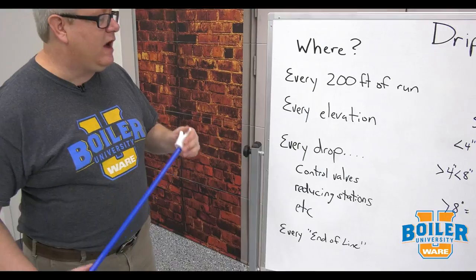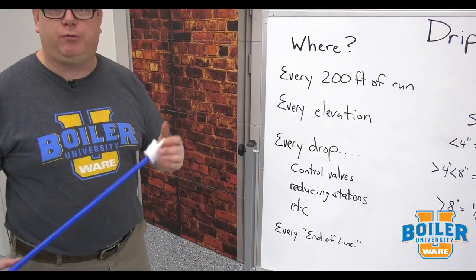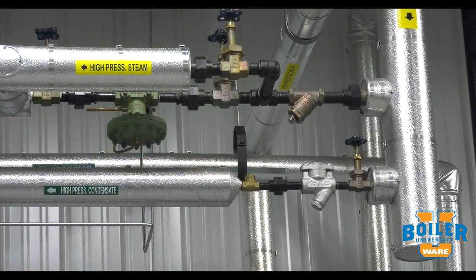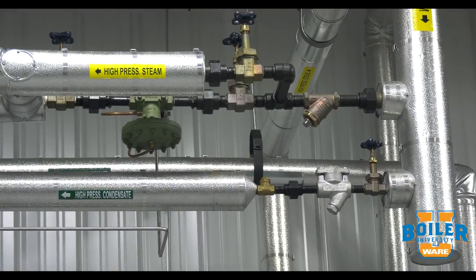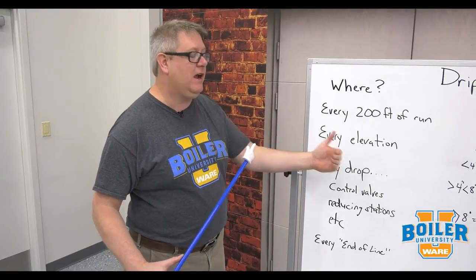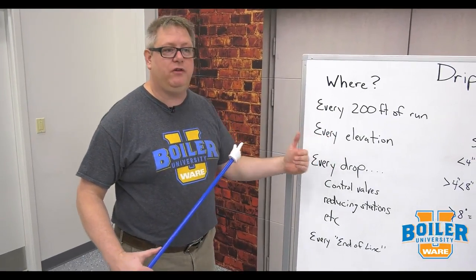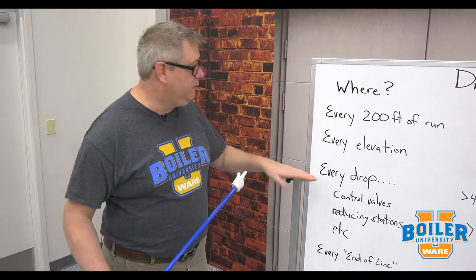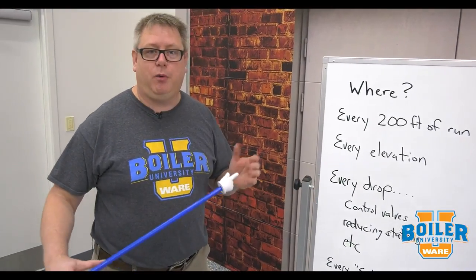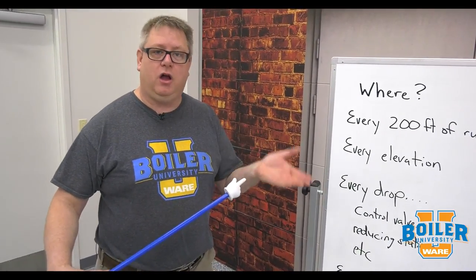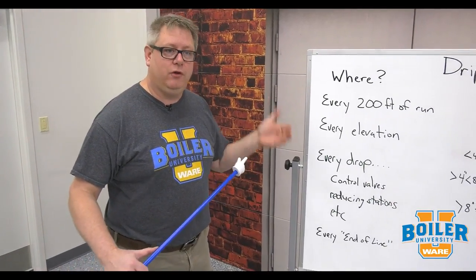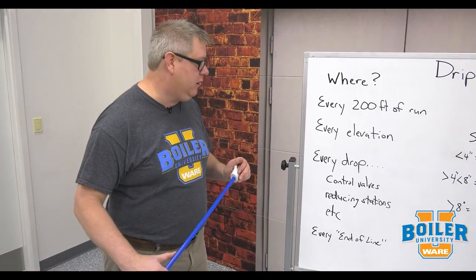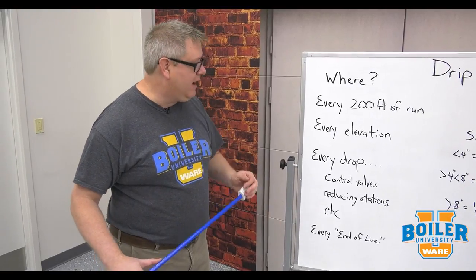At every drop — so if we've got control valves, pressure reducing stations, kettles, etc. — anywhere we're going to use steam, where we take off, we want to have a drip leg. Because presumably if we've got a control valve, at some point it's going to be closed, and when it's closed that upstream piping will flood with condensate, so the drip leg and trap keep that clear.